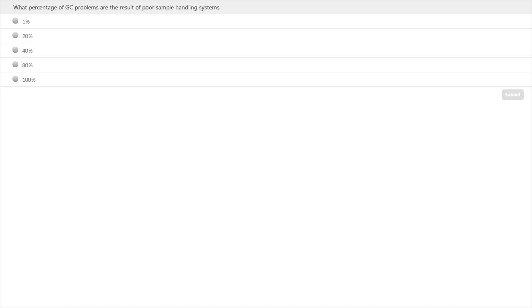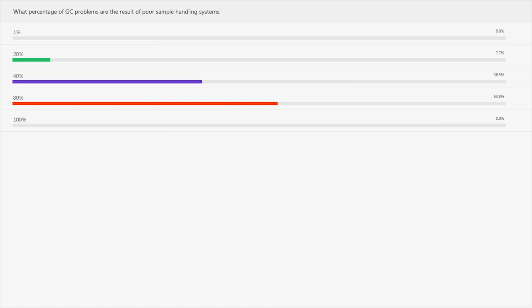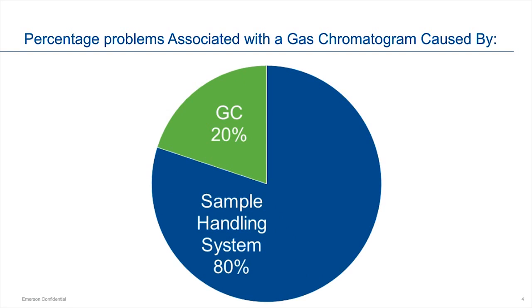We'll give you about 30 seconds to fill this out. Even if you haven't attended any webinars or seminars on sample handling or GCs, you probably know the answer. The correct answer is 80% — that's the number you'll generally hear people talk about. You can understand why it's important, because when something goes wrong, the GC becomes the prime suspect. But a lot of times it's actually the sample handling system, because it's complex with many integral parts. If you get one part wrong, the rest of the system can't compensate.